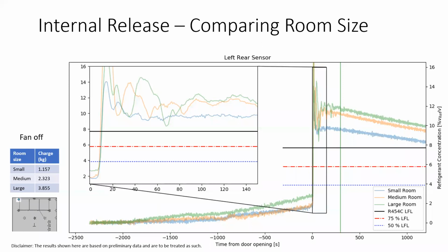We do see slightly higher peak values for the medium and large room release, but in any case, even on the opposite side of the unit from where we're opening the door, we're still seeing those values above the LFL. This specific slide was interesting to me because it showed that the sensors around the unit are similar, and the test method that we chose, opening the rightmost door, does not prevent refrigerant from reaching other parts of the room.